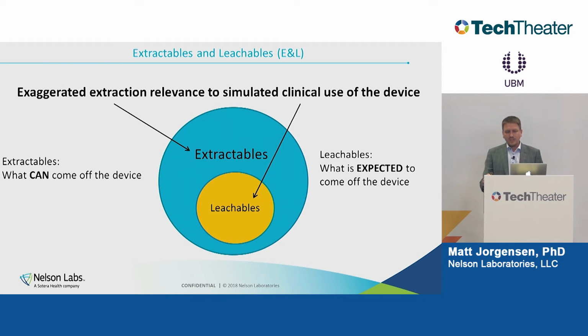The way this works to address those endpoints is that we expose the device to solvents. So we'll use water, an alcohol, and maybe a nonpolar solvent like hexane. And we see what chemicals or compounds can leave the device into those solvents. So we say, okay, those compounds could contact the body, and then we'll do some toxicological evaluation on that.